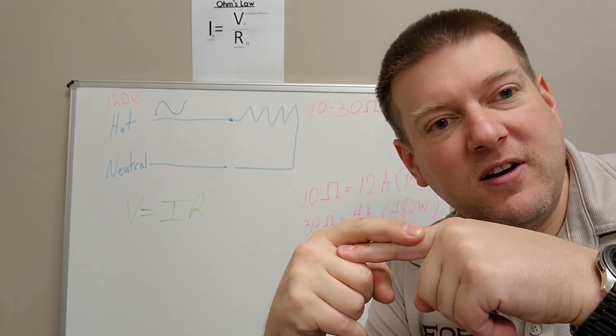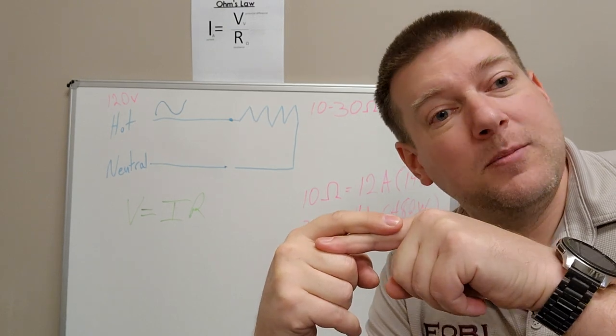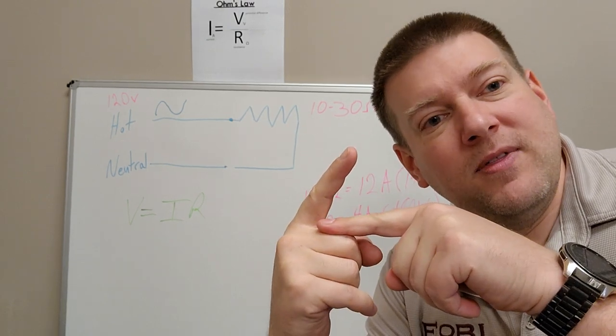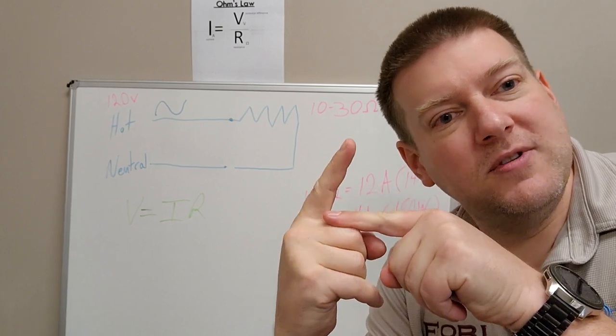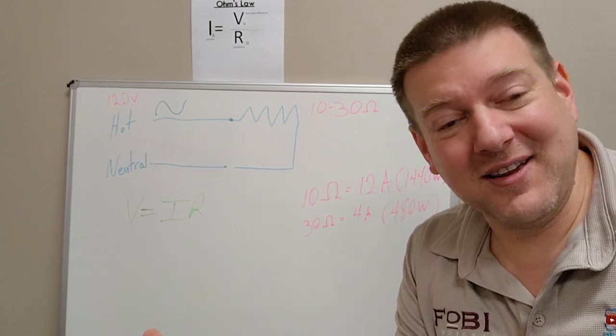So it's running full current, it gets to a certain temperature, opens up, and then it cools off, it closes, runs full current, opens up, and that is how it regulates the temperature.